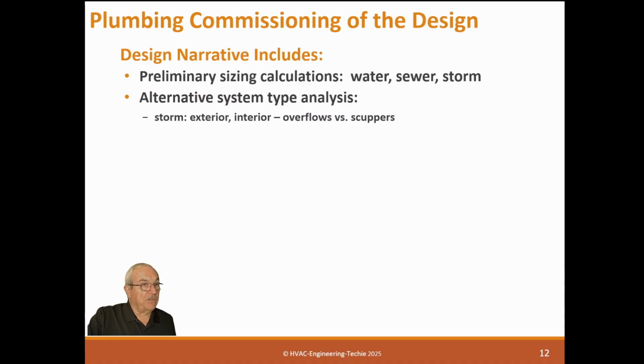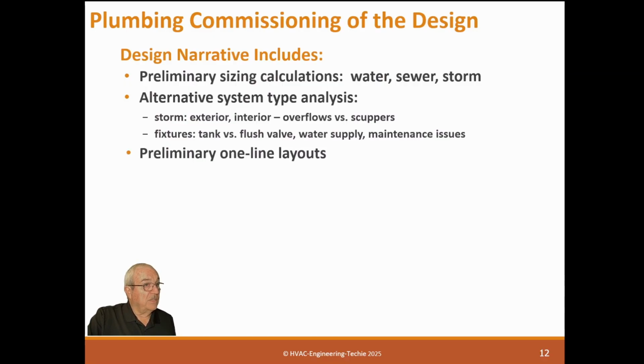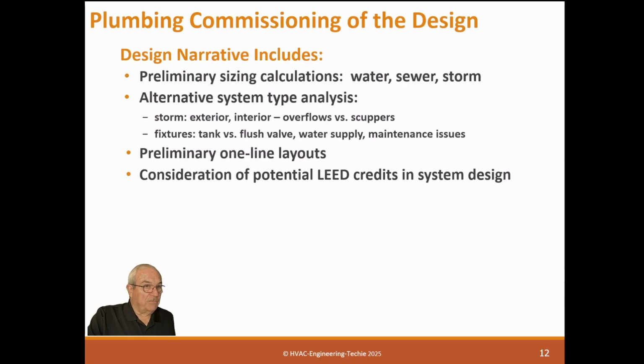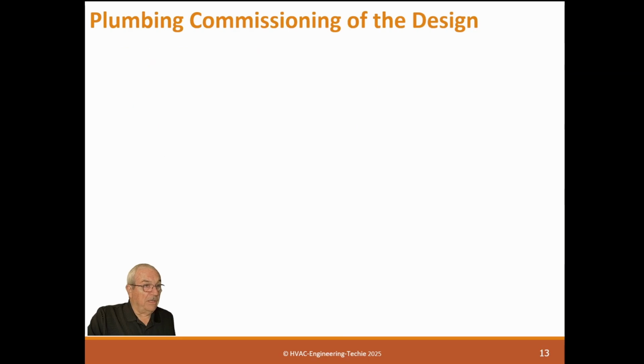So storm, exterior, interior, overflows versus scuppers, that sort of thing. Fixture, tank versus flush, water supply, maintenance issues. So all of those kind of things. Those are just a couple examples. Preliminary one-line layout, so real preliminary. This is basically where the line's going to run and all that stuff. And what this does, this gives the owner a chance to look at it before the design's actually done. And this becomes very beneficial for the designer. Because what can happen is the designer can make a decision, I'm going to do this, and the owner can say, oh, no, we can't do that. This has got to go this way. Okay, now the designer has to do it again. So this is actually a money-saving thing for the designer. Consideration of potential LEED credits in system design. What sustainability level are they going to do?